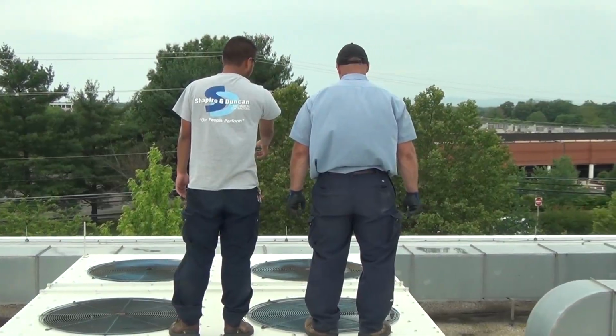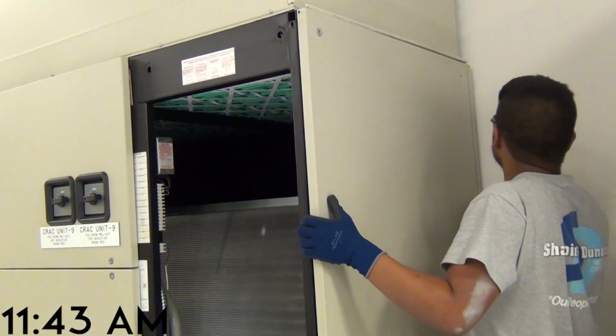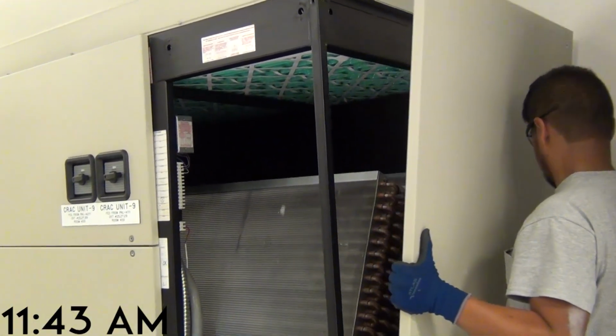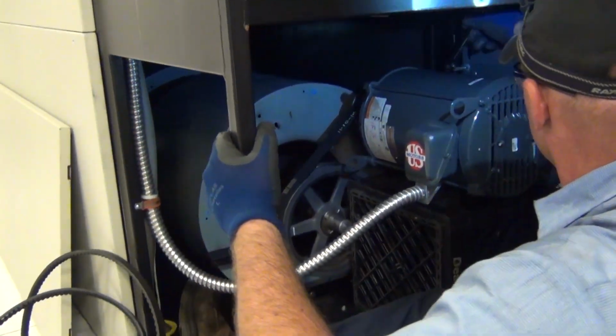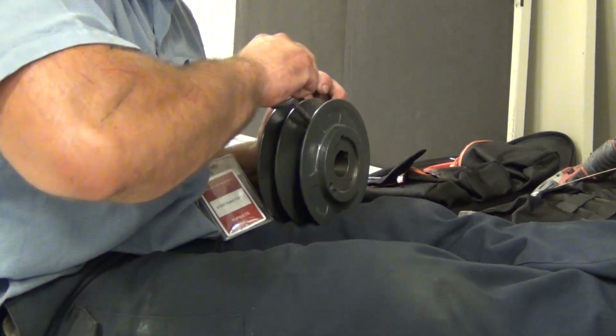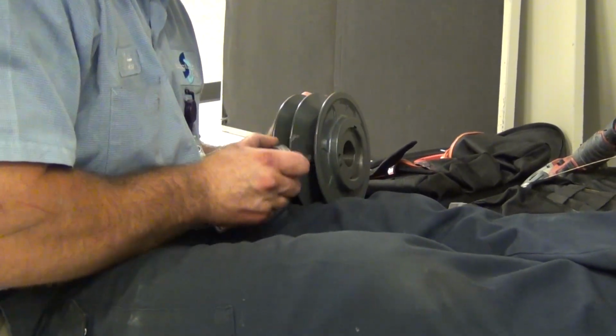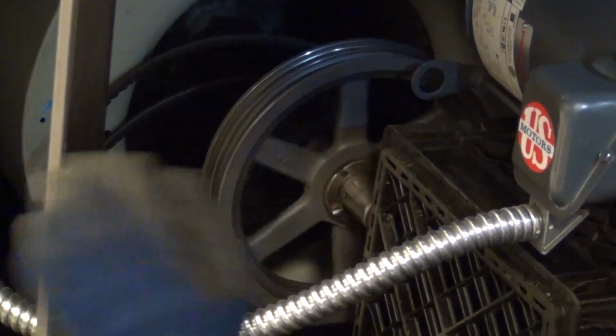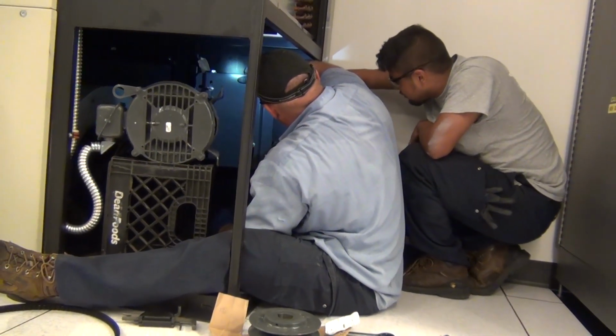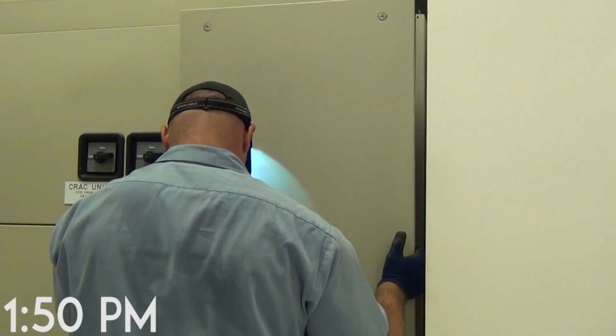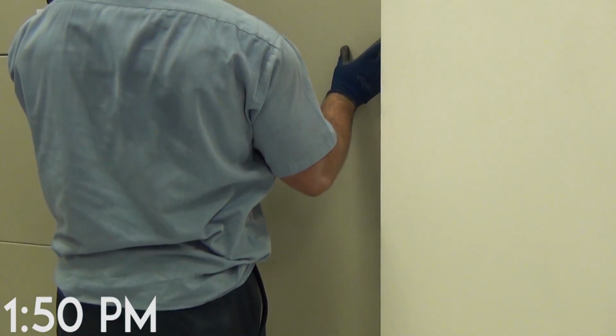Once that is complete, we move on to the last task of the day in the data room. So in this unit here, we're changing the motor sheave because it is worn out, which will result in reduced airflow. By putting a new motor sheave on, we'll get the proper airflow that it had when the unit was first installed. The day has concluded, which gives us a chance to reflect.